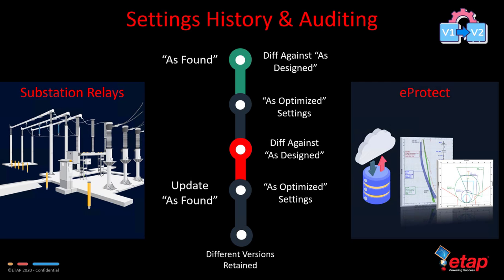Now that we've seen the retrieval and writing of relay settings in action, let's take a look at the settings history and auditing function. This may be a typical workflow, but again, not the only one, where the substation relay information is retrieved, and that is essentially indicated as found setting in the workflow. You can then create a diff or difference against the as designed, which is essentially coming from the ETAP design and analysis database. You can of course then go to ETAP and create an as optimized settings.